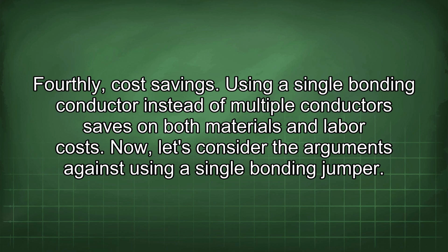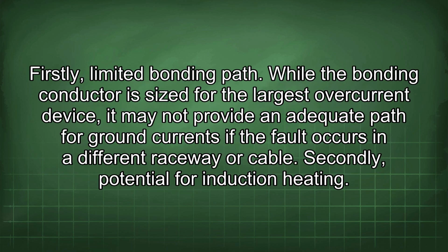Now, let's consider the arguments against using a single bonding jumper. Firstly, limited bonding path. While the bonding conductor is sized for the largest overcurrent device, it may not provide an adequate path for ground currents if the fault occurs in a different raceway or cable. Secondly, potential for induction heating.